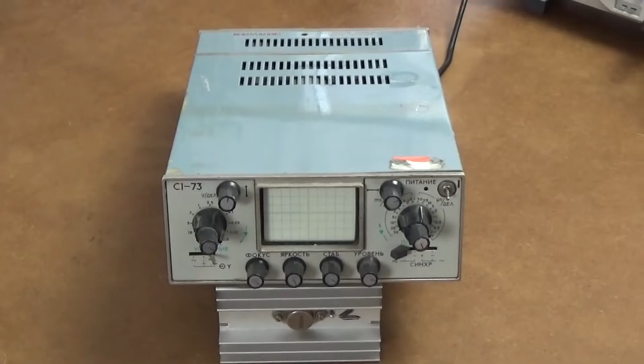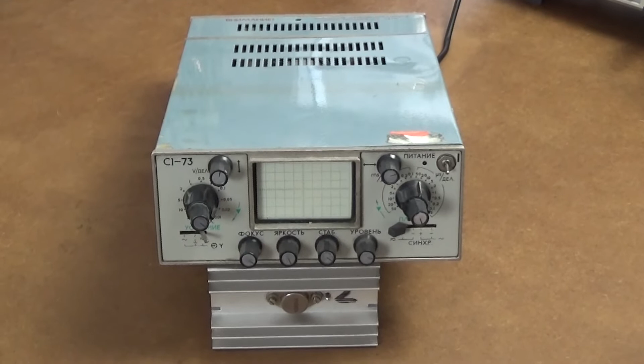One thing to consider is that for a transformer to work correctly, its core must not be allowed to saturate, which means it has to be sized accordingly. Excuse my oversimplification, but since energy is transferred to the core in packets, if we increase the frequency of the input AC, it's possible to achieve the same transformer power with smaller energy packets, meaning smaller maximum magnetic fields through the core, meaning smaller and lighter cores.